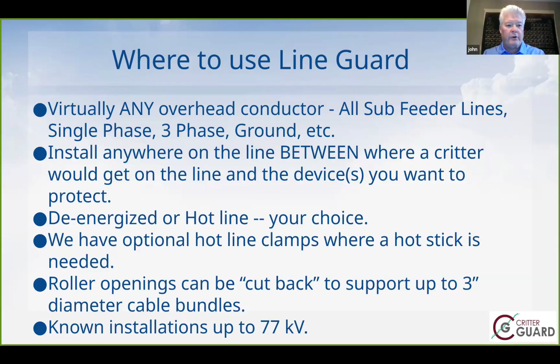I tell people all the time, don't think of this like an insulator. With other products that are precisely engineered to fit over a device, you're worried about clearances, air gaps, and dielectric constants, because you may have an induced bridge from a tree or branch landing across two adjoining phases. You don't have that problem with line guard, because they don't have to be next to each other — they can be as far away as you need. So they don't interfere with your air gap spacing on any overhead line.